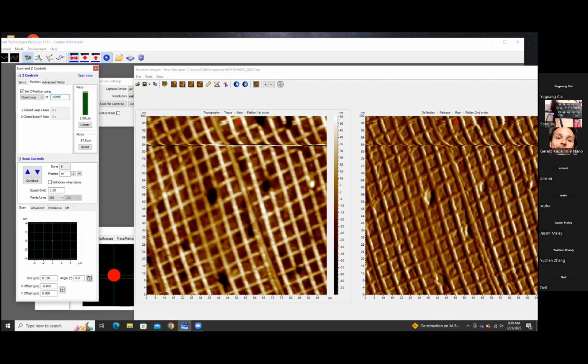Okay, I'm going to type in negative 9999, enter, and then measure the Z out. Do bear in mind that this is 200 volts DC. It will shock and bite. So please be careful if you're taking these measurements. Yes, I'm still talking. I assume I did it right. It reads positive 217 volts. So this is correct. Perfect. So we know that the positive and negative power supplies in your controller are operating properly. You can go ahead and put your Z position back to 0 just for safety reasons. You don't want to accidentally shock yourself.